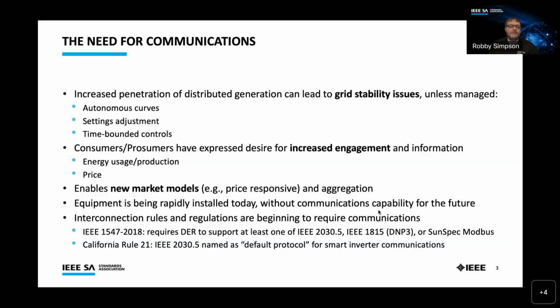And then lastly, interconnection rules and regulations are beginning to require communications. You just heard from Mamadou that the latest IEEE 1547 revision in 2018 requires a DER to support at least one of three choices when it comes to communication technologies: IEEE 2030.5, IEEE 1815, often called DNP3, or SunSpec Modbus. Each of those has a particular niche that they specialize in.